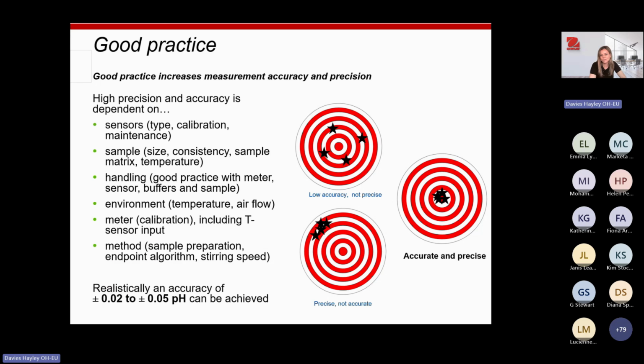So good practice when you are testing pH of a solution. What kind of accuracy can be expected when you're measuring pH? Well, that all depends on a number of factors and how well the meter and the probes have been looked after. So for instance, the sensors, are you using the correct type of sensor? Have they been calibrated regularly, and have they been maintained appropriately? The sample, is it the correct size or volume? Is it the correct consistency? Is it the correct temperature? Or is the temperature of the sample known?